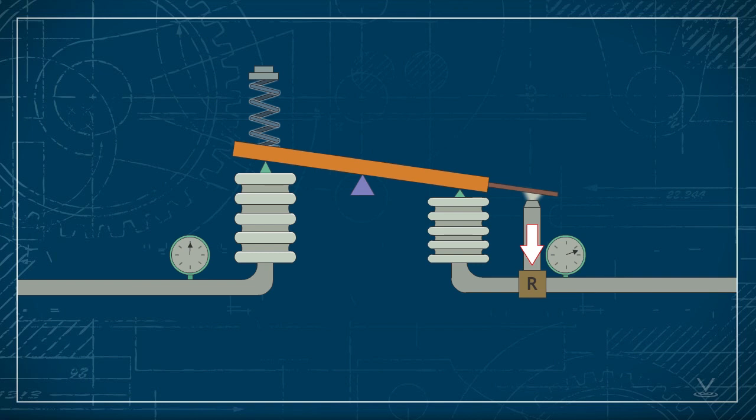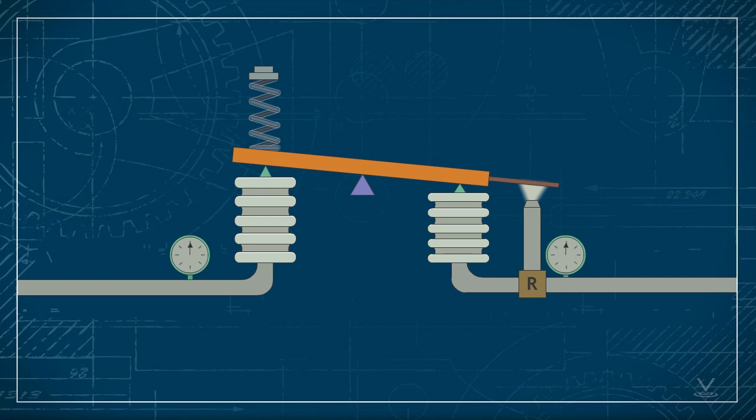The relay converts the change in back pressure to an output that reflects the increase. The increase in output is supplied to the feedback bellows, which expands and brings the controller to a balanced condition that reflects the difference between input and setpoint.